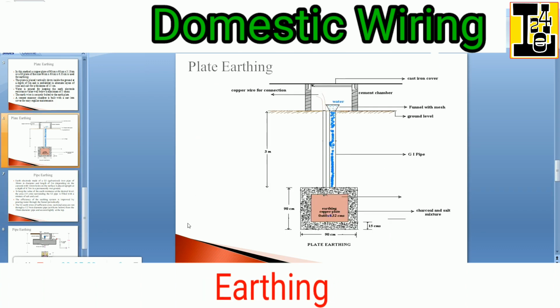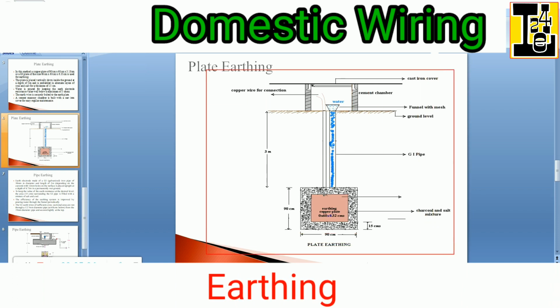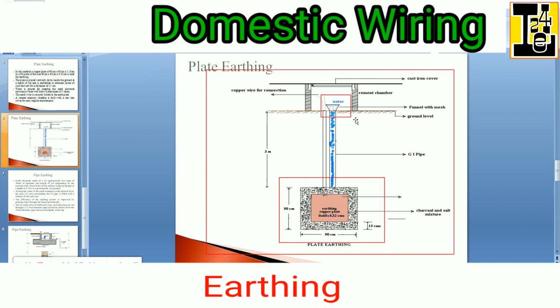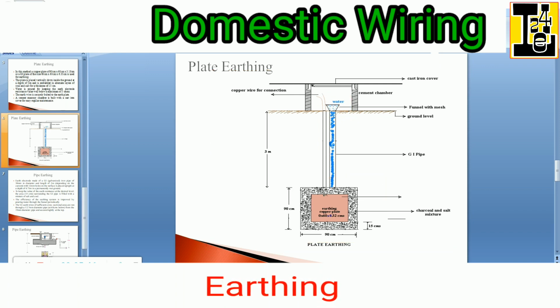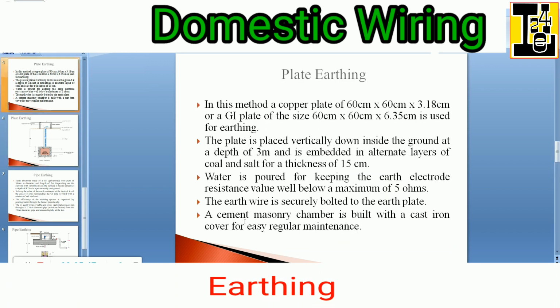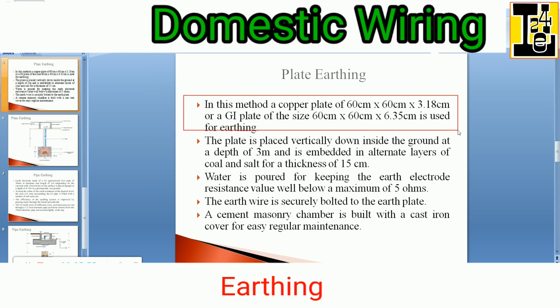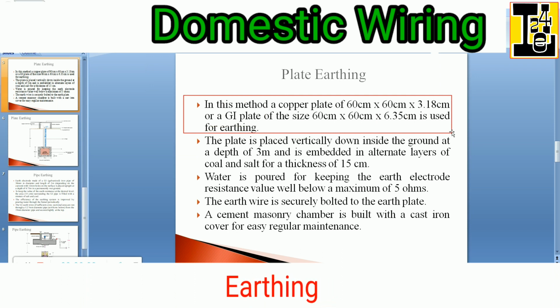Let us go through plate earthing. This is the arrangement of plate earthing, where you can observe the plate over here at the bottom inside the ground. This is the funnel arrangement which is provided to pour the water. Let us have the explanation for this. This is the method where a copper plate of 60 centimeter by 60 centimeter by 3.18 centimeter, or a GI plate of size 60 by 60 by 6.35 centimeter, is used for earthing.